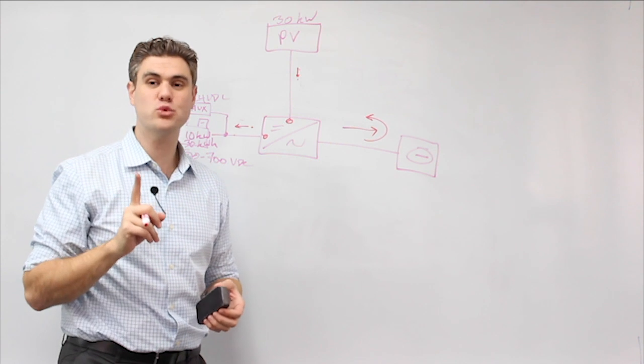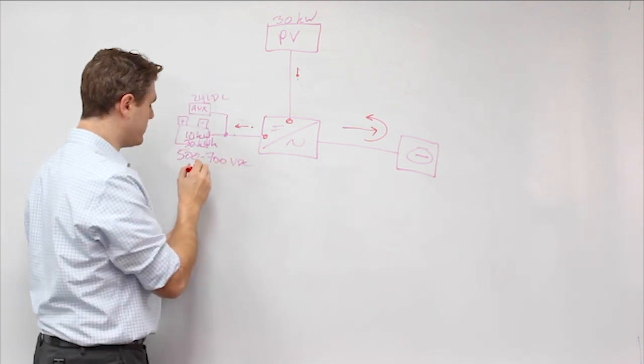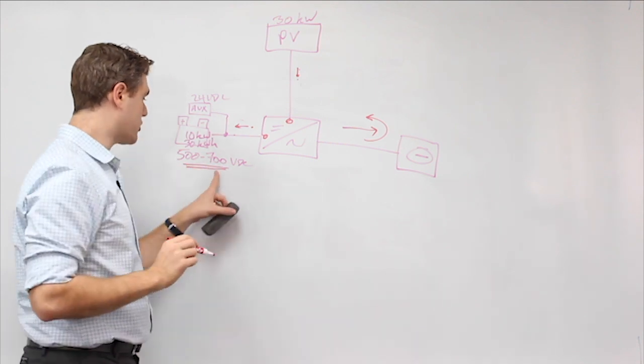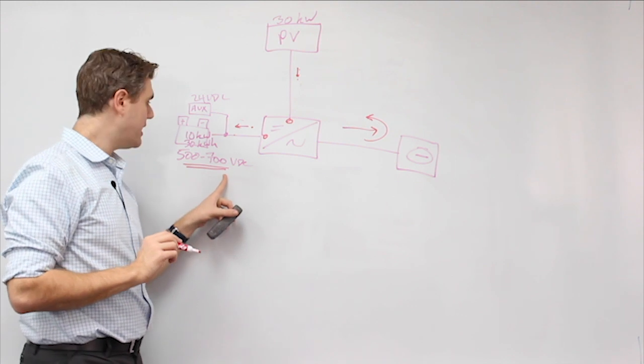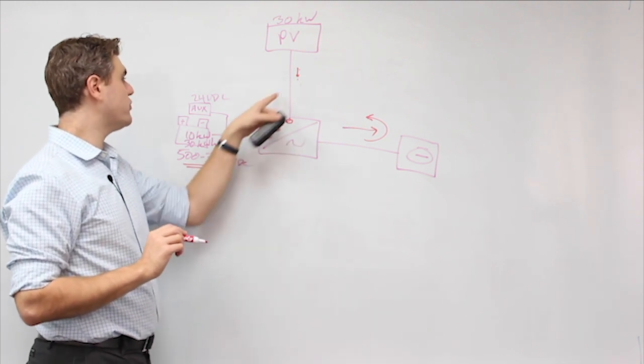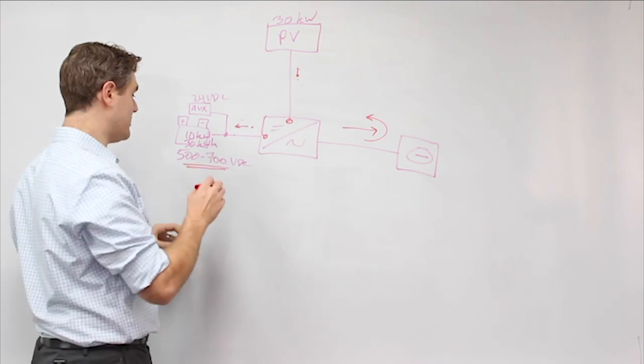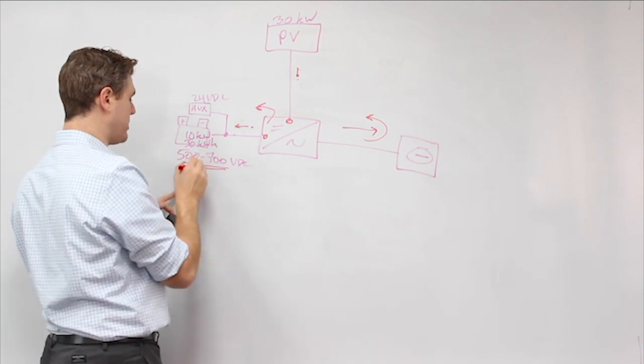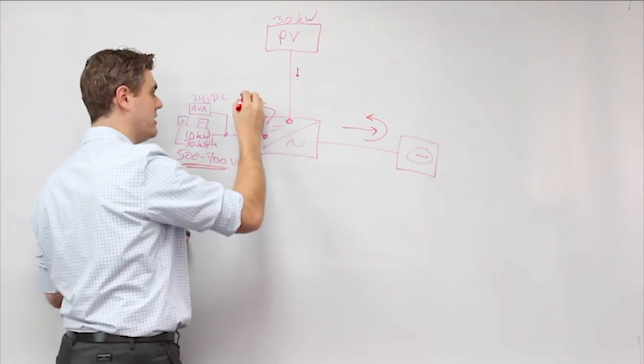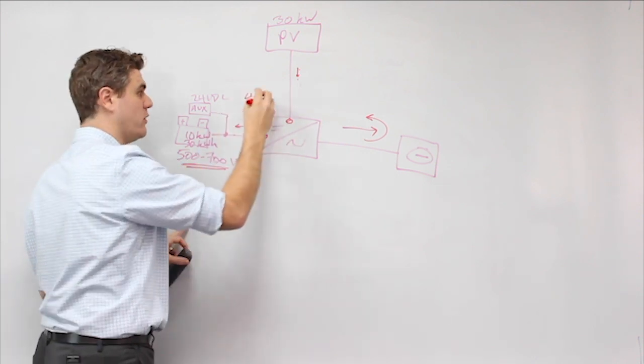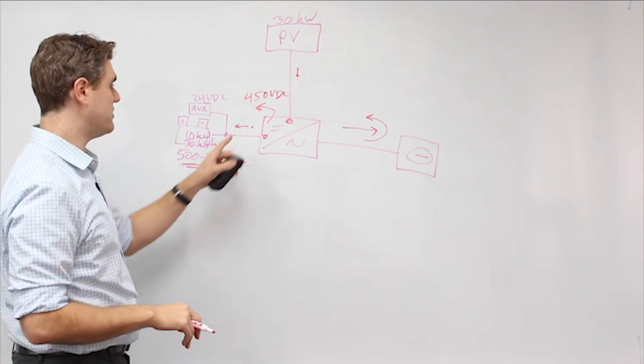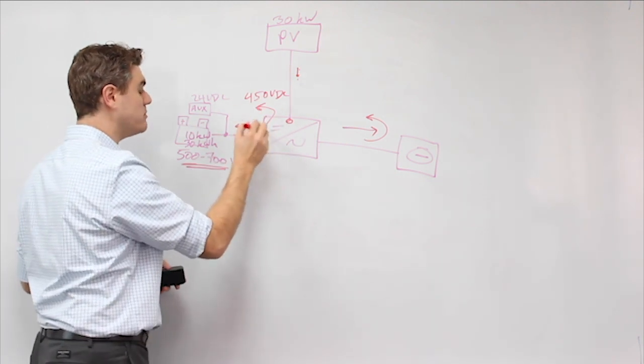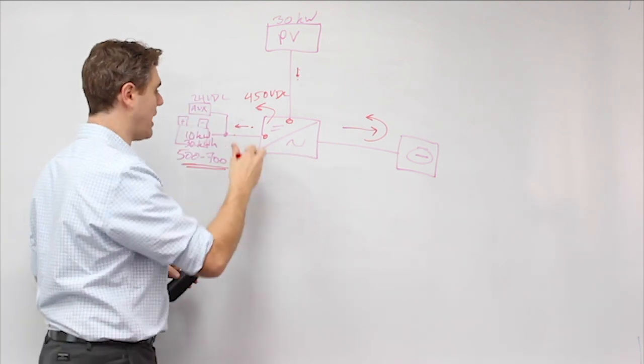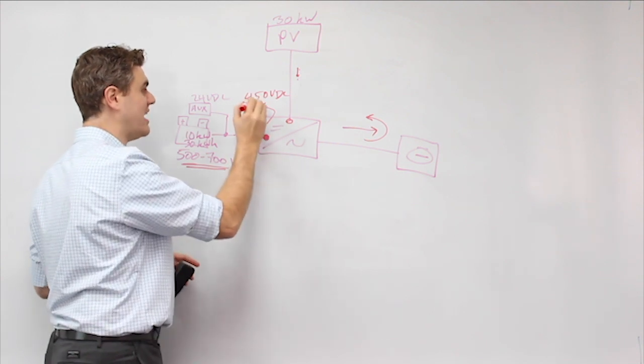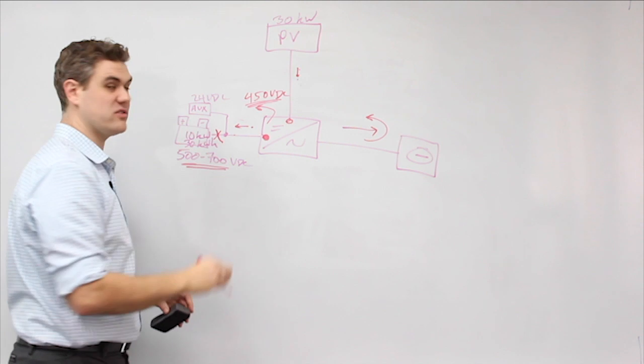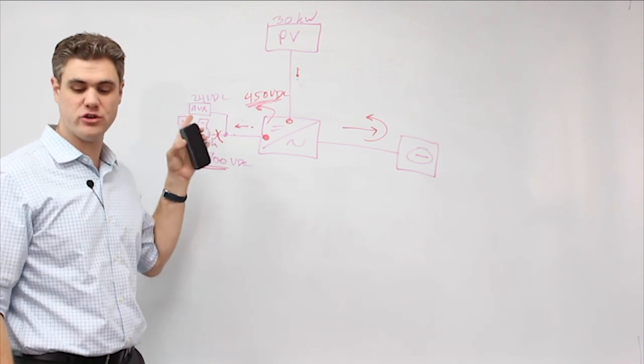It uses something called a voltage regulation mechanism. It knows that this battery operates across this voltage range, 500 to 700 volts. And just before these arrows line up and have the same magnitude, the inverter sets the voltage to something below the minimum operating voltage of the battery. In this case, since the minimum operating voltage of the battery is 500 volts, it sets it to 450 and says, hey, these arrows are getting close together. Now I'm controlling the voltage. I am the voltage source. I am controlling the voltage at this port, at this bus. I am setting it to 450. This guy shuts off. It can't operate. It physically cannot charge or discharge from the grid.